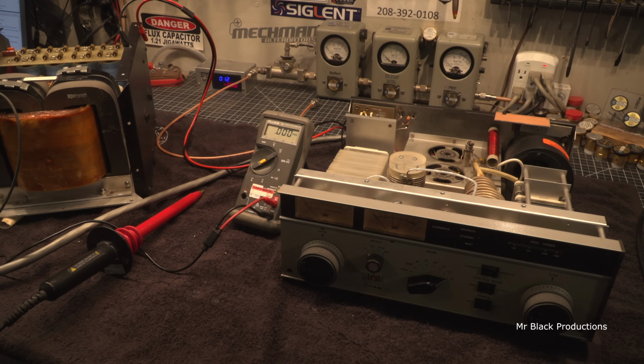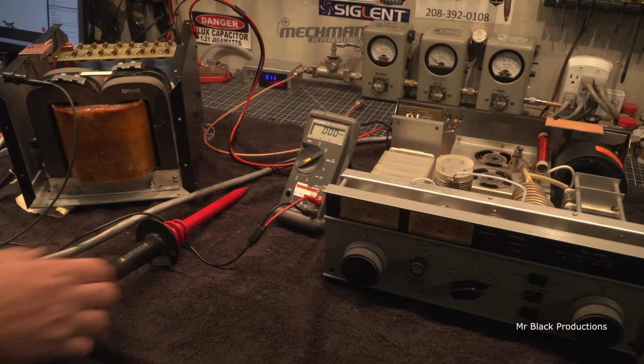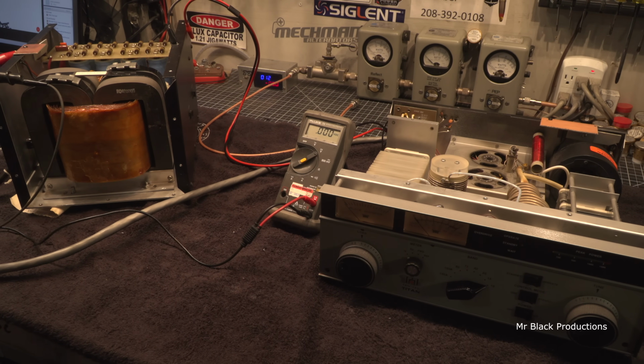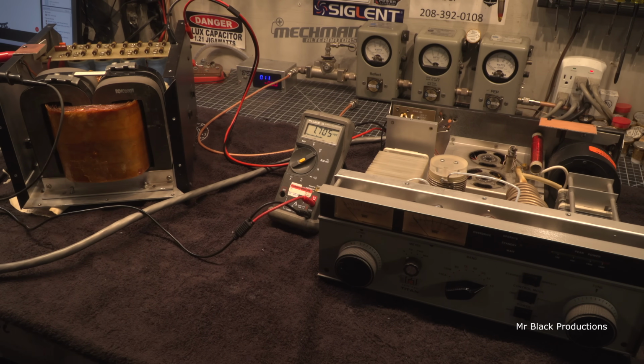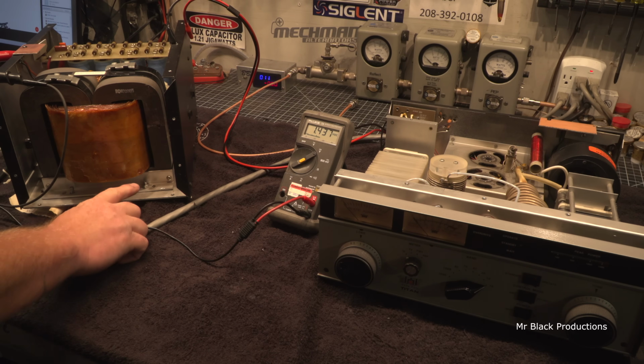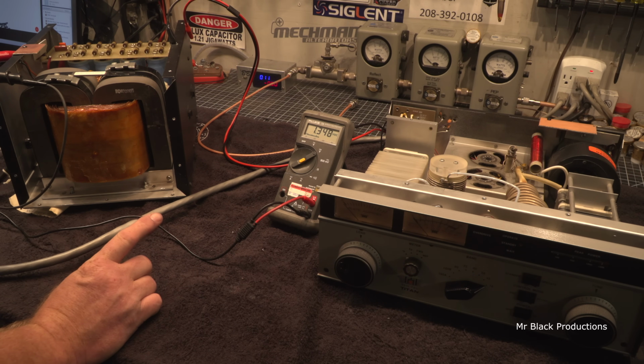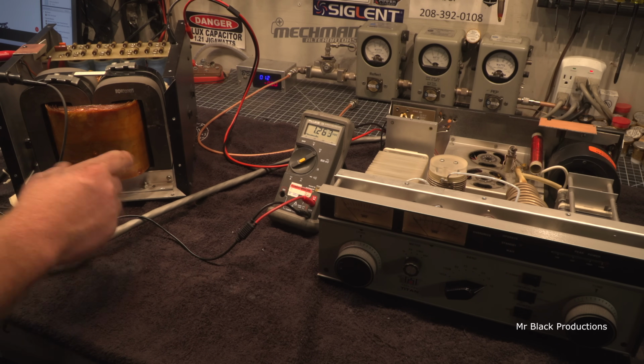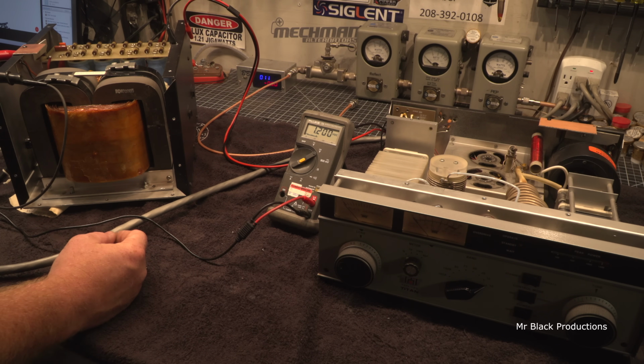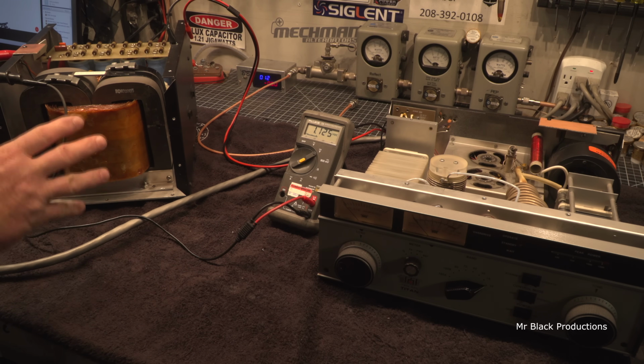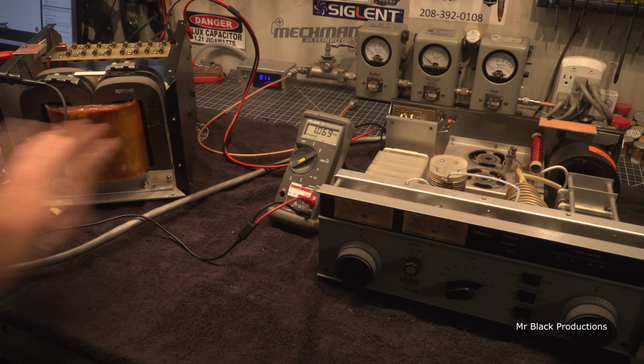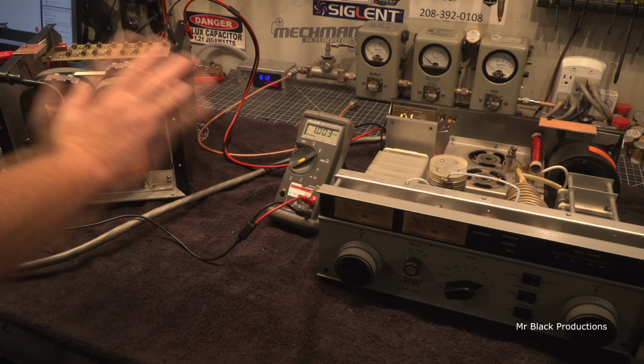For the sense of safety, after I verify this is fully discharged down to 0, we'll short out the power supply and put the lid on it. The transformer is only held in by 1 bolt at the moment, so the core has common ground. Once we get this bled down, I'll put the case on for safety, and we can set this aside because everything in here is good.